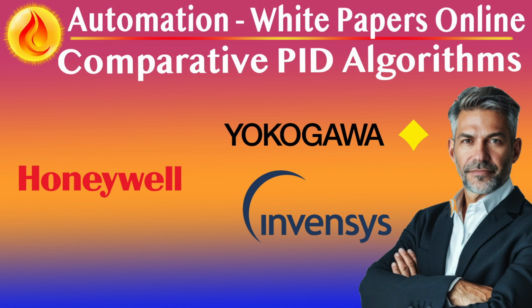Real-world implications and best practices. Retuning is mandatory when switching controller brands or types, even if PID settings seem identical. Set point response behavior is algorithm dependent. Tuning for load rejection does not guarantee good set point tracking unless the algorithm explicitly supports it. Use filtered derivative to preserve valve life, reduce actuator wear, and suppress false alarms. Choose algorithm forms based on loop purpose.